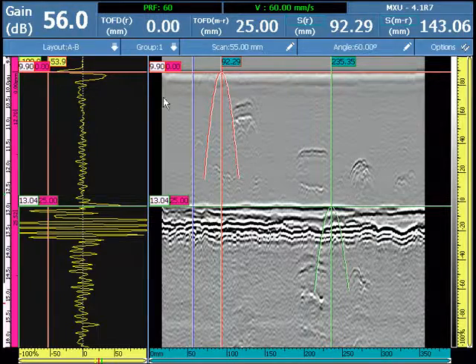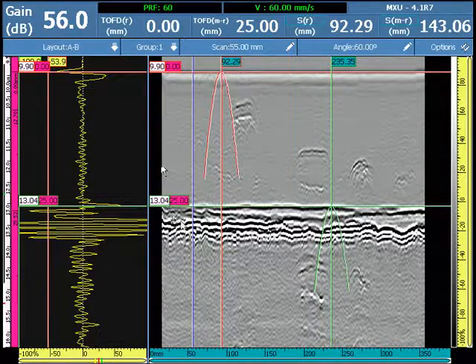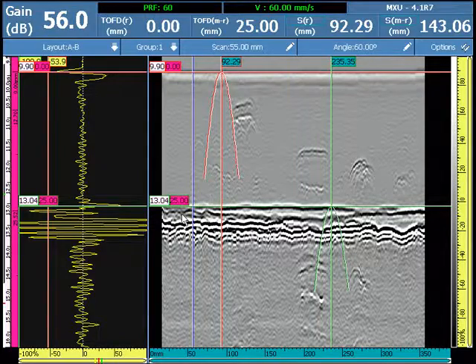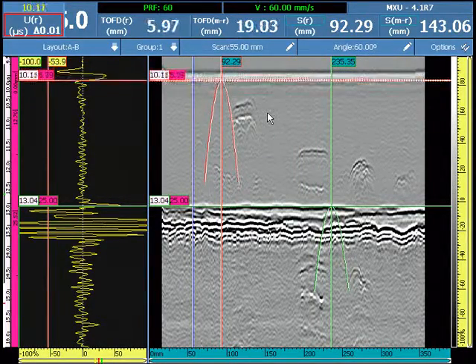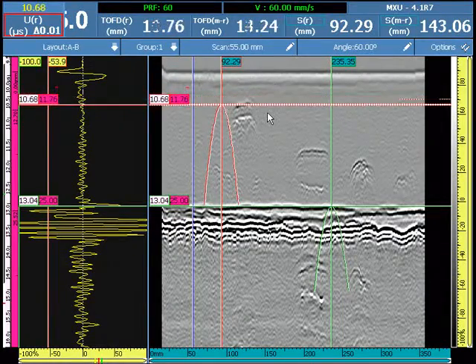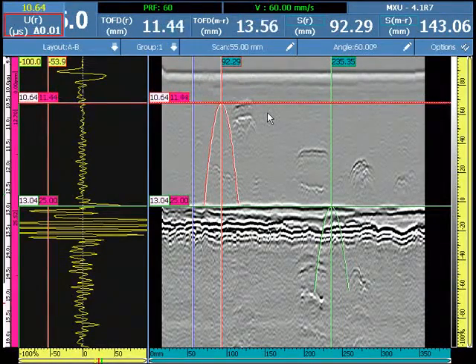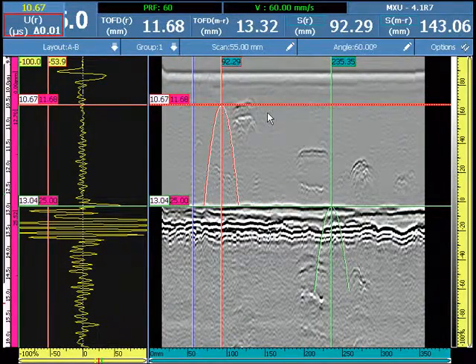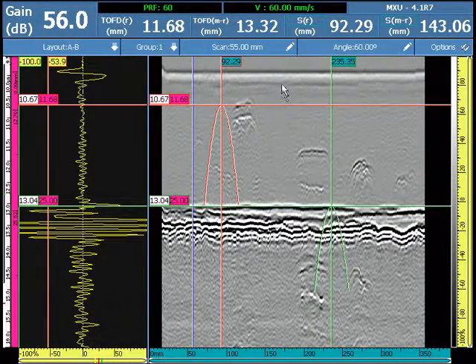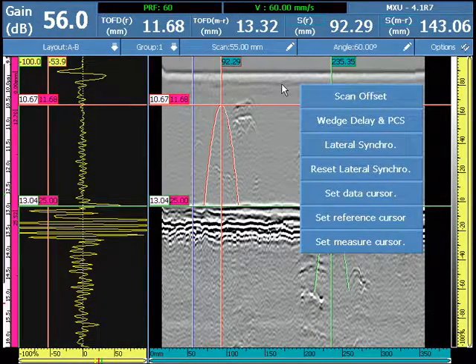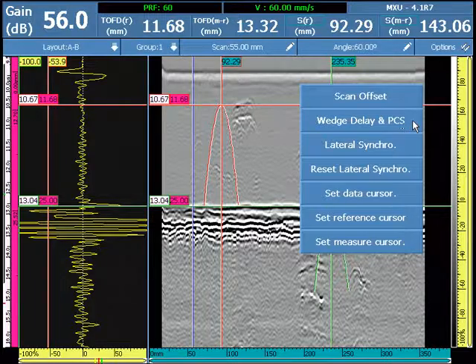In the area between 0 millimeters and the component back wall or thickness of 25 millimeters, the screen is linearized and precision measurements can be made on the A-scan and B-scan. At any time, the cursors can be repositioned and the calibration updated.